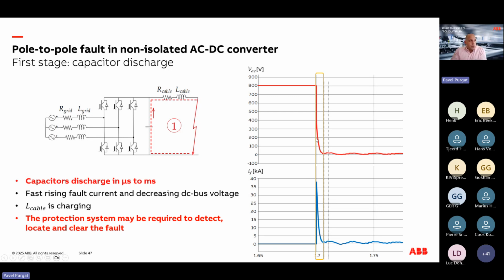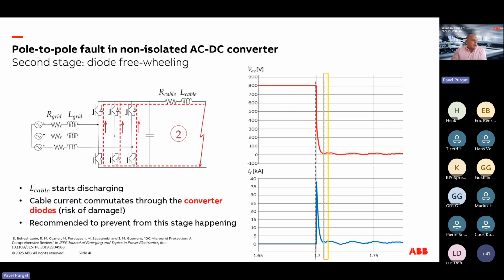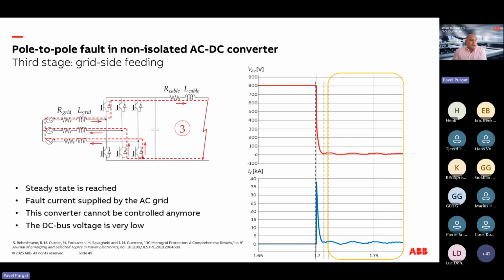After the current drops, the voltage is dropping as well. Likely the undervoltage protection of the converter kicks in and the switching stops. However, the diodes that we have here, here, and here will continue to conduct current, and we are getting to the secondary phase where the current is commutating to the diodes, and the diodes will then continue to supply the current to the fault. And we need to check if this energy is enough to trigger the fuse, or if the fuse I squared t is as specified by the converter manufacturer.